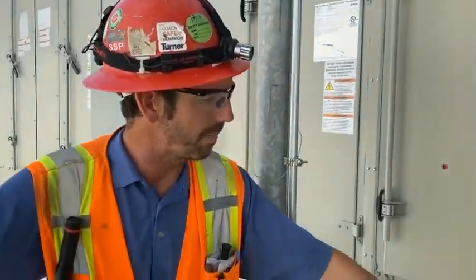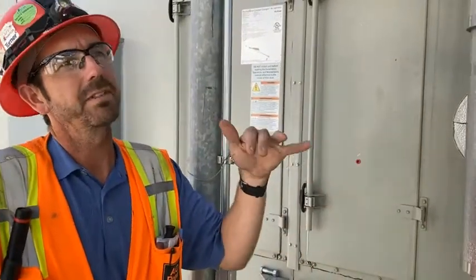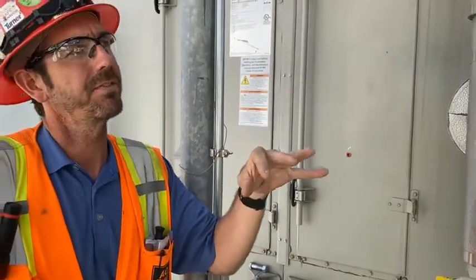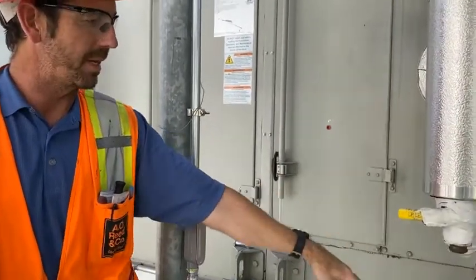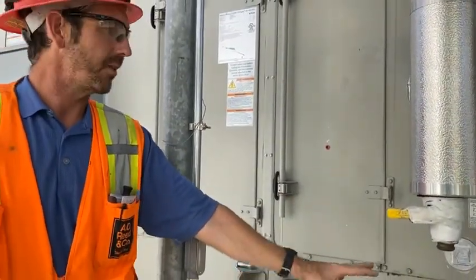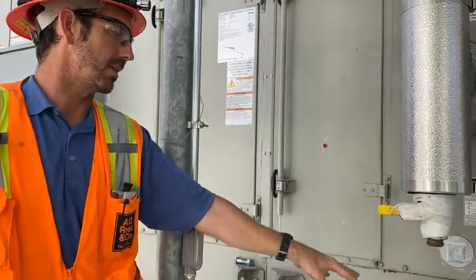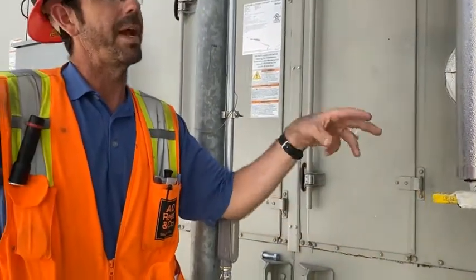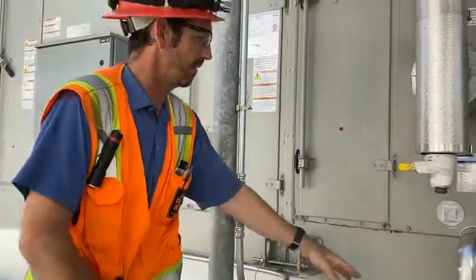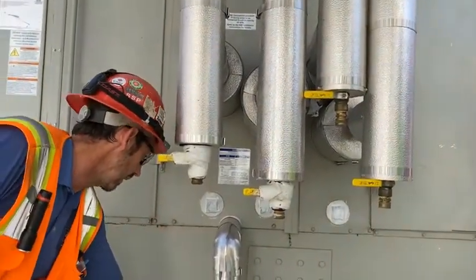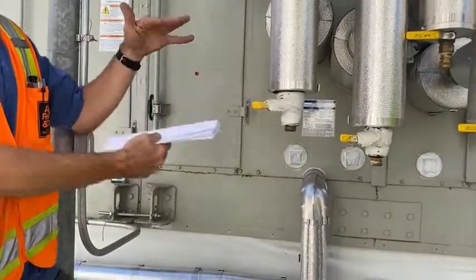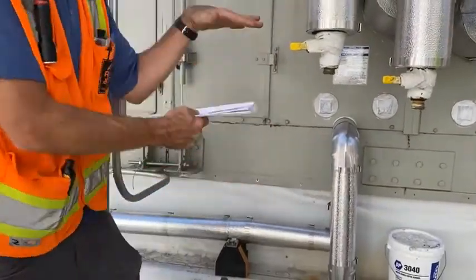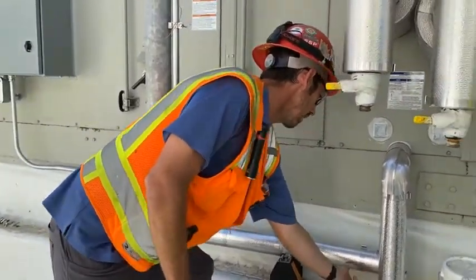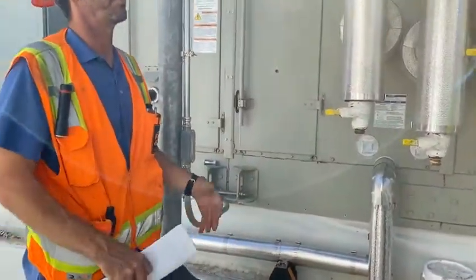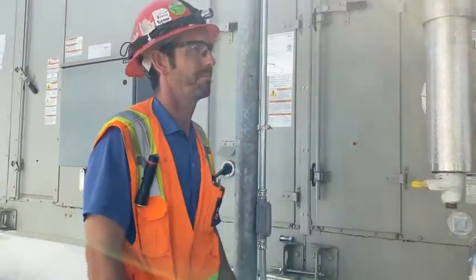Guys, I forgot when we were at this air handler, we're walking by the condensate trap here. In our submittal data that was provided to us from the manufacturer, they give us the minimum dimensions of the trap, okay? So if you ever have to modify this trap, make sure you build it back to the same dimensions or follow the manufacturer's trap height dimensions. They give you the differences between the inlet and the outlet here. It just has to be minimum, right? We can go longer so we can use this curve. We just have to meet those minimum distances from the bottom of this pipe to the bottom of that pipe too, okay? That information is in the submittal information. It tells you the height to build all the traps, okay?